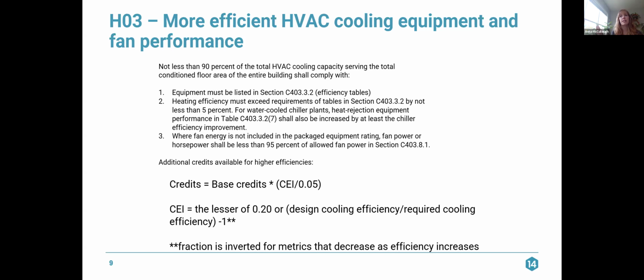Again, there are additional credits available. The lesser of 0.20, I'm sorry, it's the base credits times CEI divided by 0.05. And CEI is the lesser of 0.20 or the design cooling efficiency divided by the required cooling efficiency minus 1. Asterisk, asterisk. If your metric decreases as efficiency increases, kilowatts per ton comes to mind, then you invert that fraction when you're calculating your CEI.